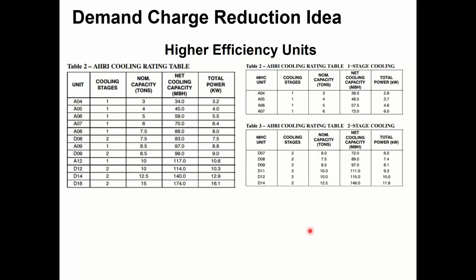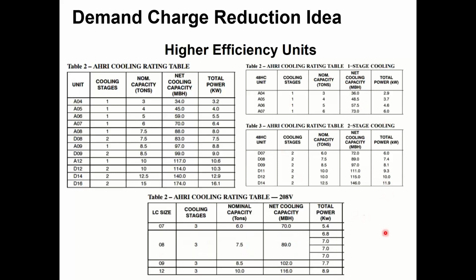If you have higher efficiency units, you'll typically have lower demand charges. So for example here, I'm showing you a standard efficiency unit in this table over here, high efficiency over here on the right. Let's say I take a proverbial 10-ton 2-stage unit. It's 10.3 kW, which will go into my demand charge. If I take a 2-stage 10-ton unit that's more efficient, it's 10. So it goes from 10.3 to 10. Is it a huge demand reduction? No, it's 0.3. But it still helps a little bit, especially when I have multiple pieces of equipment. If I go from this mid-efficiency unit up to an ultra-efficient 10-ton unit, it goes down to 8.9. So 10.3, 10 kW, 8.9 kW. So the more efficient my unit gets, typically the lower the demand charges will also be. That's not the reason why I'm doing it.